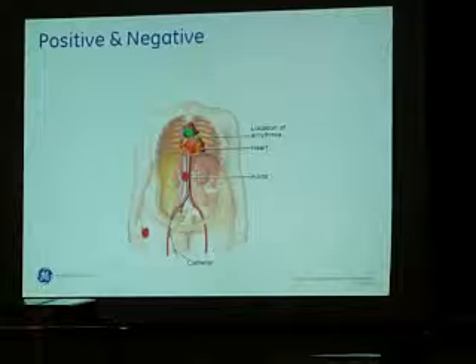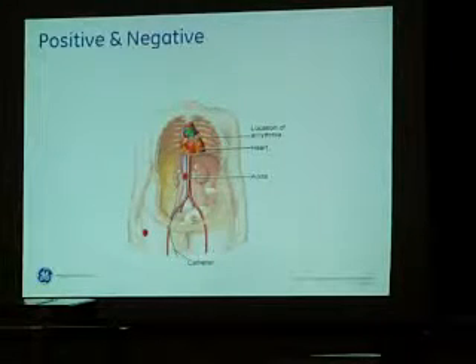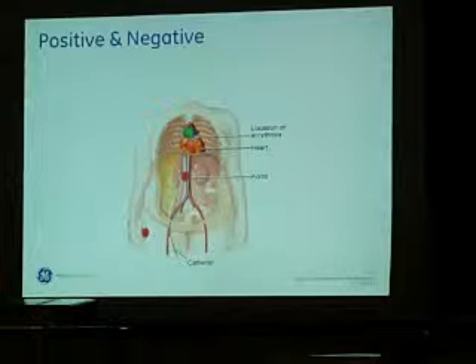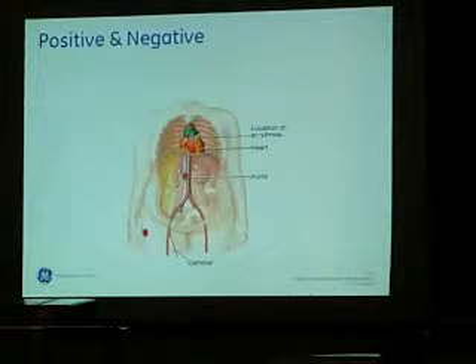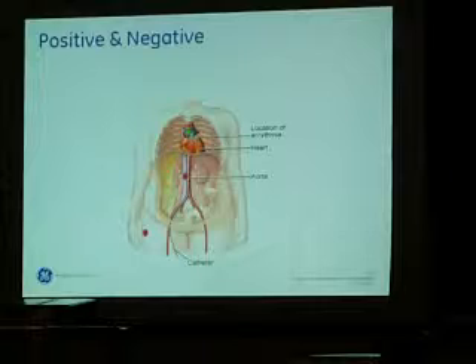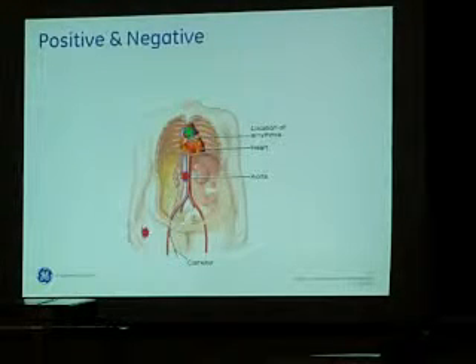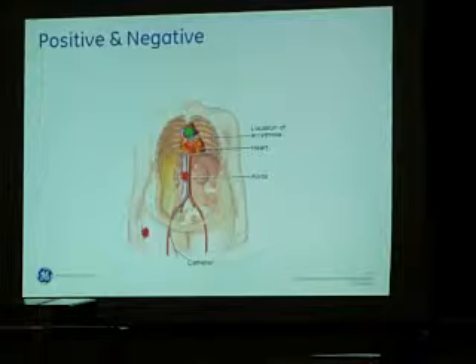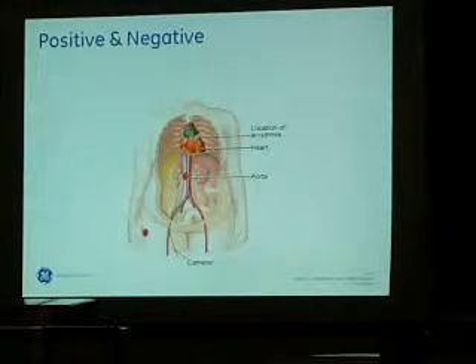Another thing we can do is called a Wilson common terminal, or Wilson central terminal, or whatever. It actually uses the ECGs on the outside of the body, the patches, as its negative grounding reference. The problem with that is that it's on the outside of the body, and the skin sort of acts as a natural filter from all the crud that's going on in the room. So now you've got signals from the inside of the body that are amplified extraordinarily so you can see what's going on, and they're all screaming with noise coming from your IV pump, your mapping systems, and the fan that's keeping your computer cool.